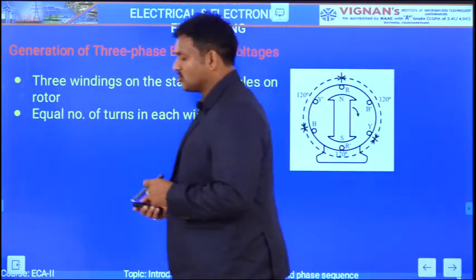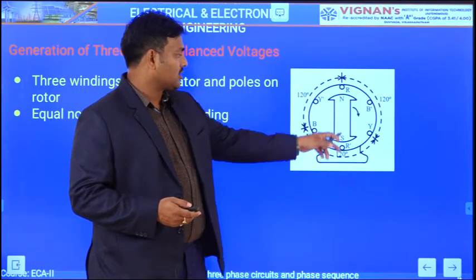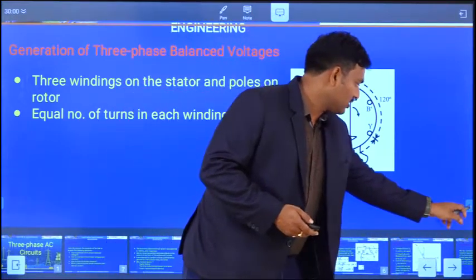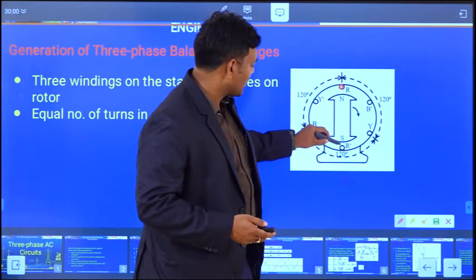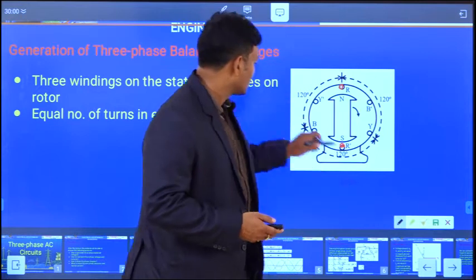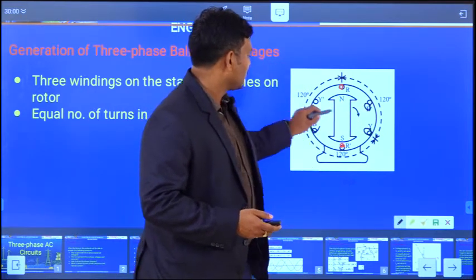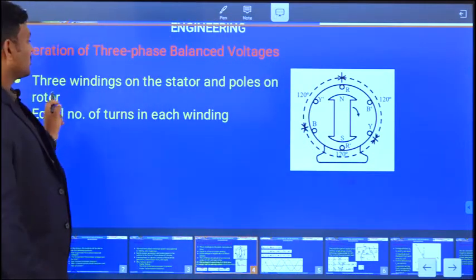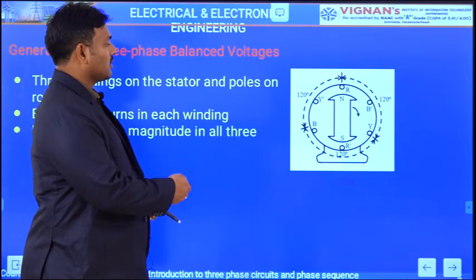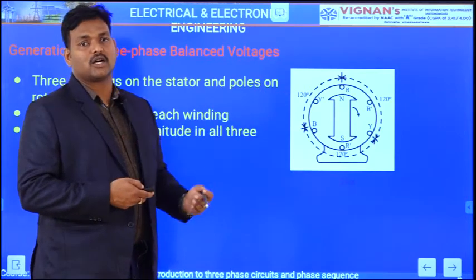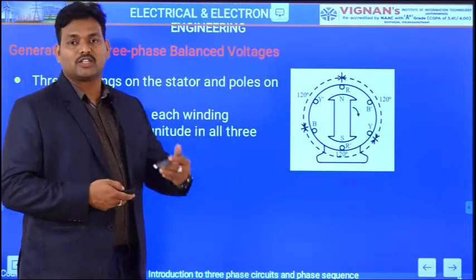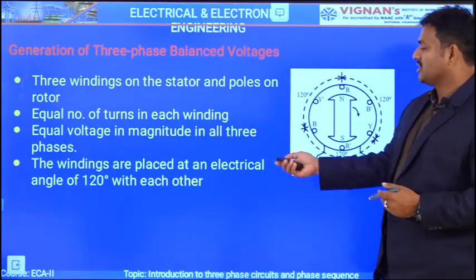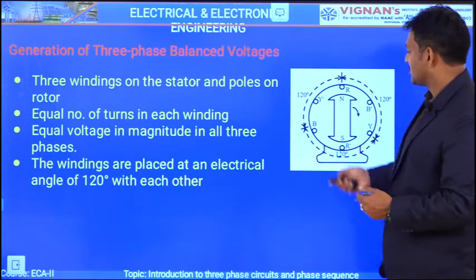To generate three-phase balanced voltages, you need a setup with a salient pole and an armature having three windings — R-R dash, Y-Y dash, and B-B dash — placed mutually 120 degrees apart electrically. These three windings on the stator have equal number of turns to produce equal voltage magnitude in all three phases. The poles are on the rotor. The windings are electrically displaced by 120 degrees from each other, and therefore the three-phase voltages in each phase are also at 120 degrees from each other.